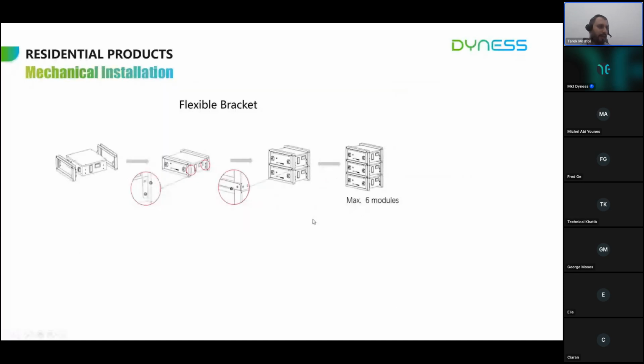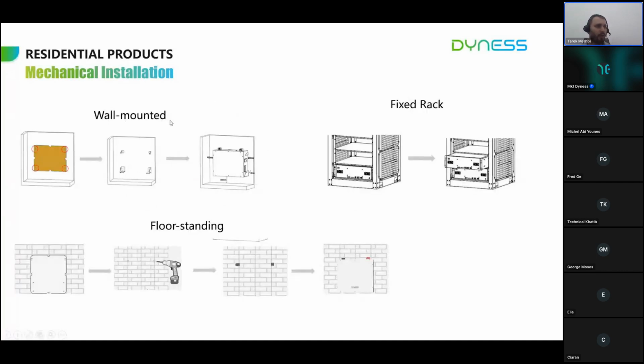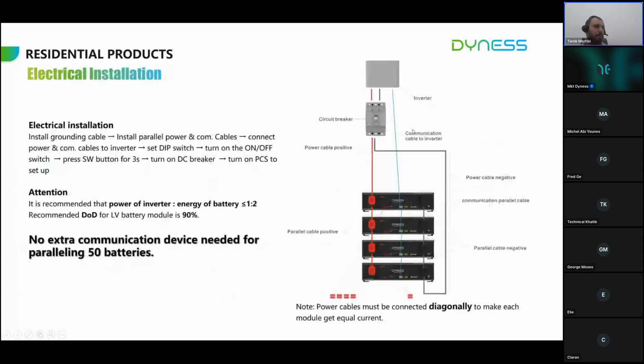How to install the DL5.0C? It can be installed as a rack, or wall mounted, or floor standing. So we have various methods of installation: wall mounted, floor standing, and fixed rack. For electrical installation, we recommend to our customer that the positive cable should be at the top of the batteries and the negative cable should be at the bottom, which means it should be connected diagonally to make each module get equal current.